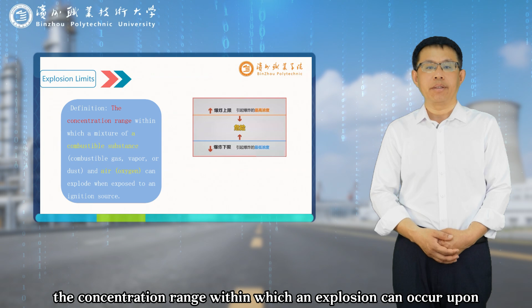For flammable substances, including mixtures of flammable gases, vapors, or dusts with air or oxygen, the concentration range within which an explosion can occur upon contact with an ignition source is known as the explosion limit. Note that the lower the lower explosive limit level of a flammable mixture and the wider the explosive limit range, the greater the risk of explosion. Mixtures with concentrations above the upper explosive limit, UEL, must never be considered safe, as they become hazardous as soon as additional air is introduced.